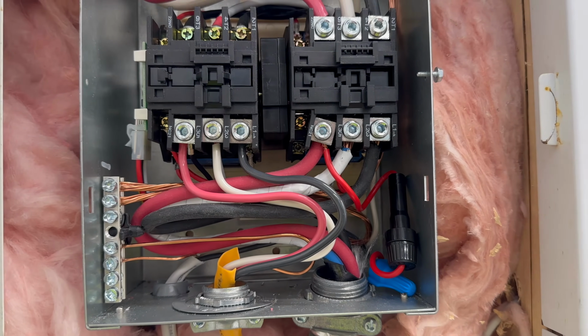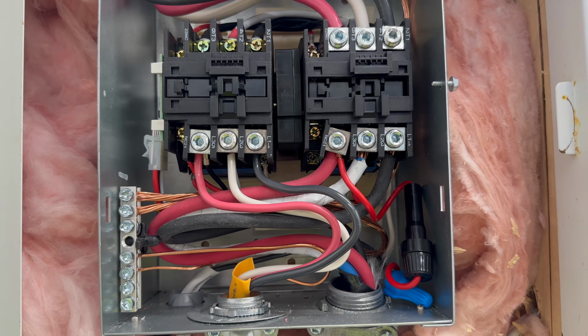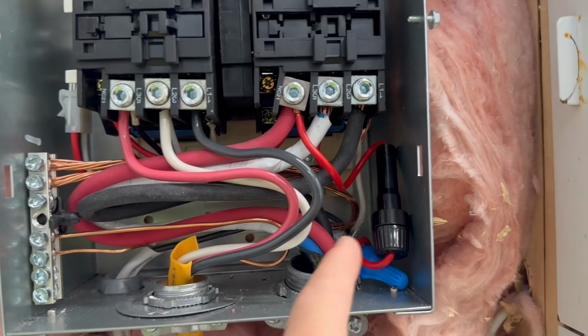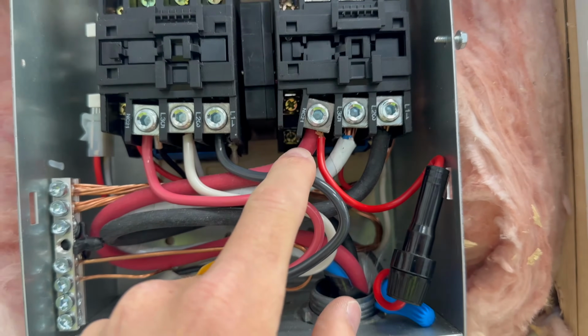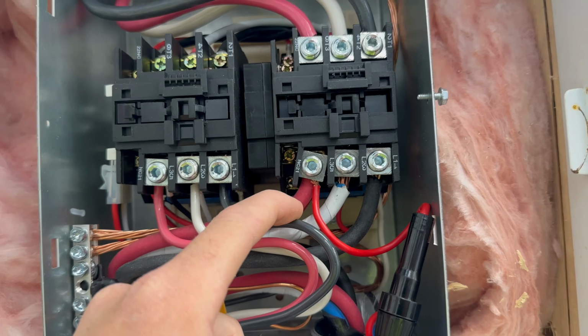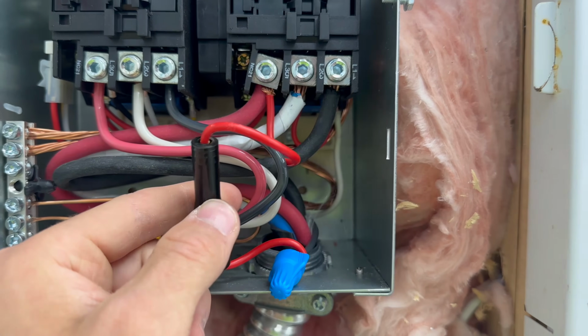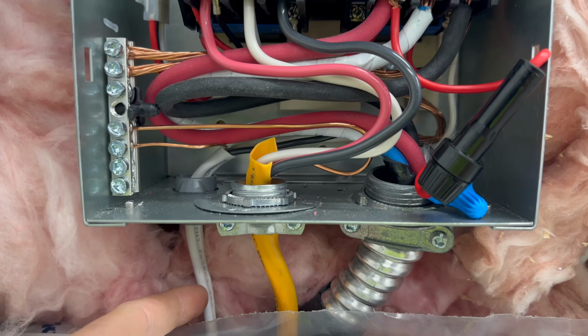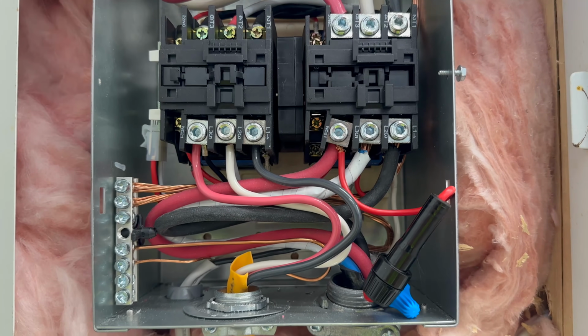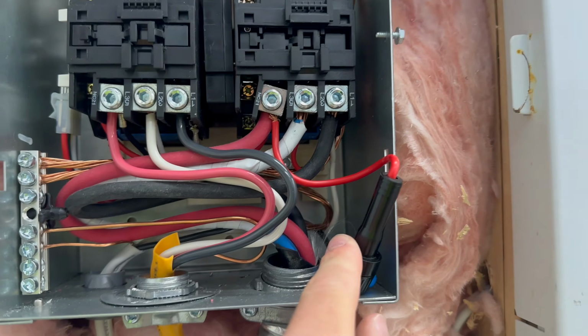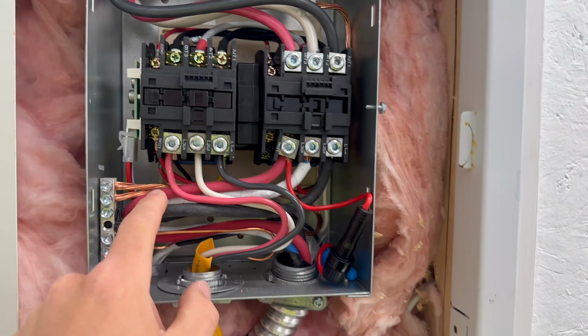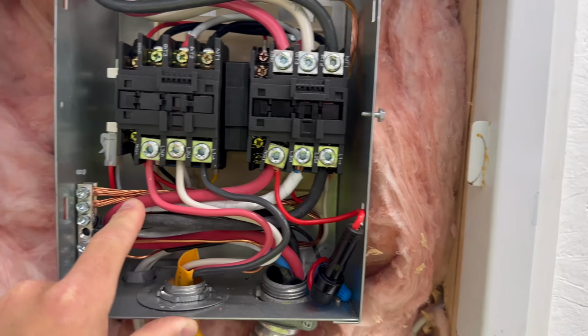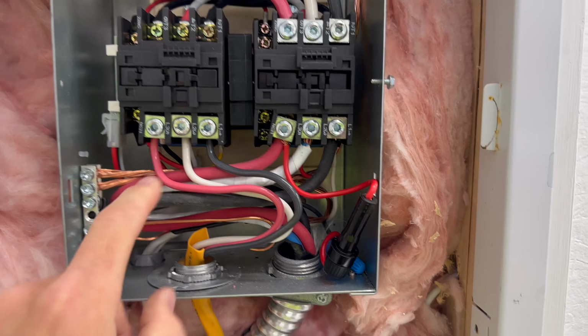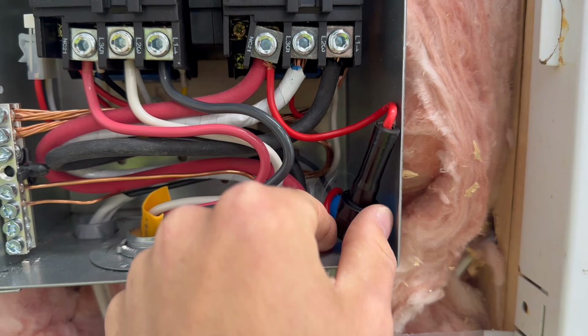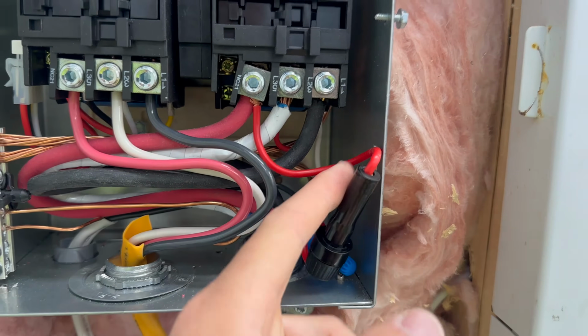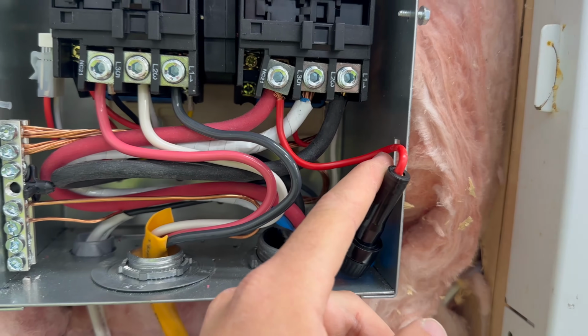But how does the generator actually know when to start? I showed you where the 120 volts ties into that relay out there. That is coming off of right here, which is tied onto one of the hot legs of the BC Hydro side. So this right here is where it connects to this white wire, which makes its way out to the generator where it ties into that relay. I have a fuse installed in here as this is only 14 gauge wire, but this circuit could be fed up to 50 amps and the wire would overheat if something happened before the breaker would trip. That's why we have an inline fuse right here, which is fused at I believe 3 or 4 amps. So should this wire lose power, the generator will start.